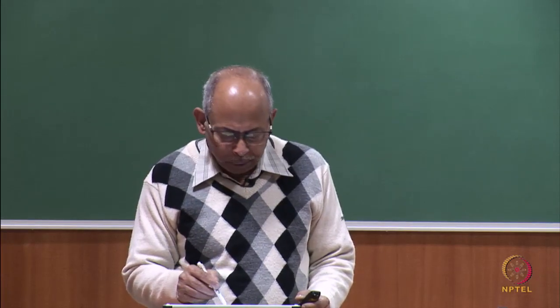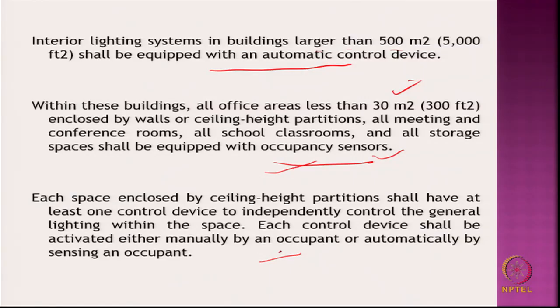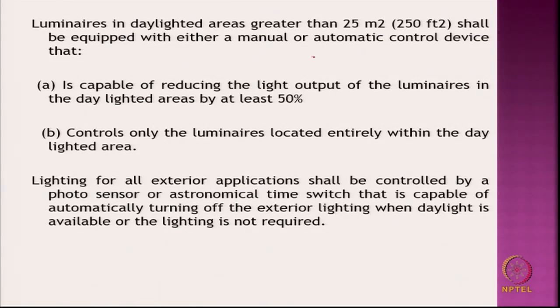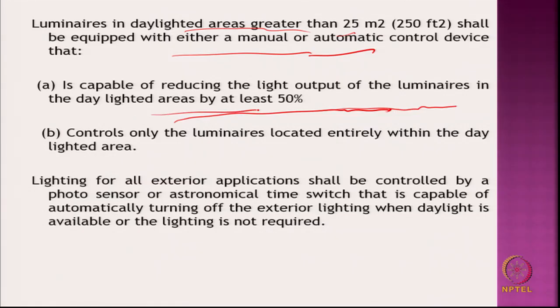So, it also says that you can put in a control. Each space enclosed by ceiling height partitions shall have at least one control device to independently control the general lighting within the space. Each control device shall be activated either manually by an occupant or automatically by sensing the occupant. Then it also talks about light fittings: luminaires in daylighted areas greater than 25 meter square shall be equipped with either a manual or automatic control device. So, a luminaire is the light fitting. It should be capable of reducing the light output of the luminaires in the daylighted areas by 50%. So, try to utilize maximum daylight, with controls only for the luminaires located entirely within the daylighted area. Lighting for all exterior applications shall be controlled by a photosensor or astronomical time switch that is capable of automatically turning off the exterior lighting when daylight is available or lighting is not required.